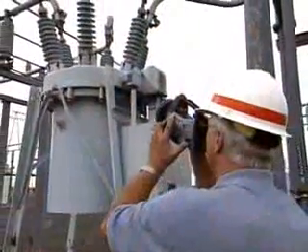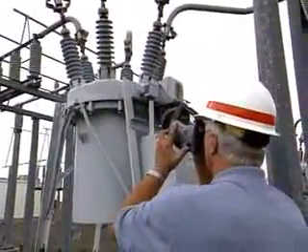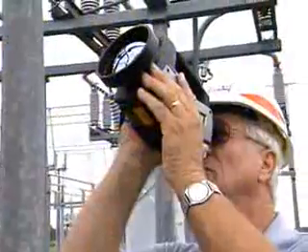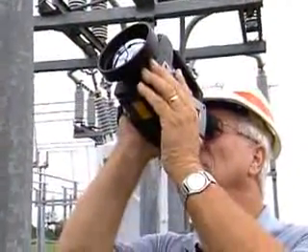When I go in the station, I scan the station, I look for anything that's out of the ordinary — an anomaly that would show up. A hot spot is elevated in temperature, and it will cause a problem. The FLIR camera lets us see this problem.